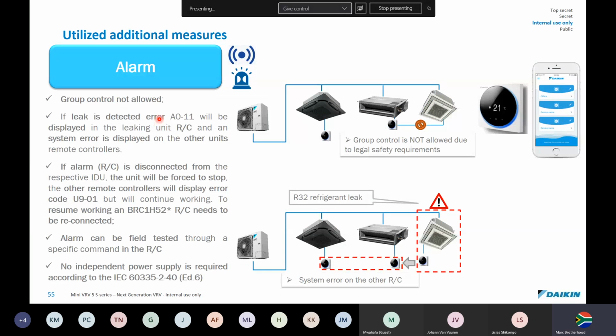Now, importantly, group control is not allowed because you cannot, even if it's an open area, daisy chain units together. Each unit needs its own remote control because each unit has a potential leak, and this unit might leak and there's no remote to warn. This might be 25 meters of cable away from this remote. So group control, unfortunately, is not allowed.